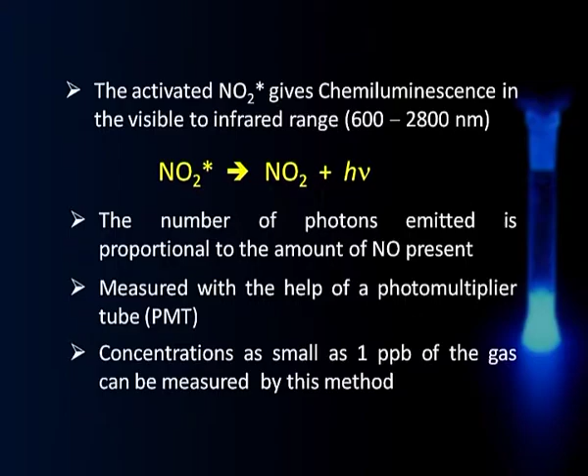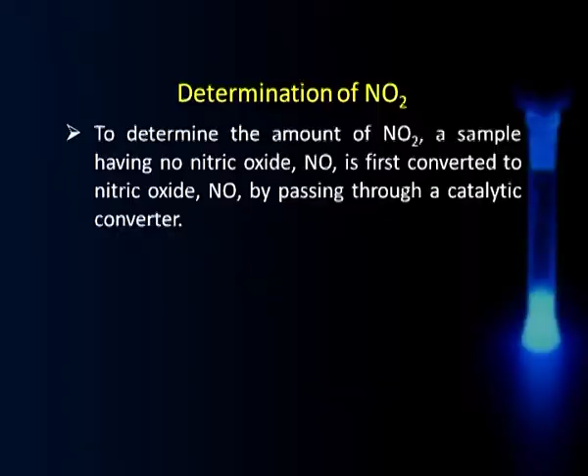Let us see how we determine NO2 in a sample of polluted air. NO2, we know, cannot be determined as such. So, to determine NO2, we first ensure that the sample of air we want to measure does not have any NO in it. Thereafter, this air sample containing NO2 is made to pass through a catalytic converter, which does the job of converting NO2 to NO.